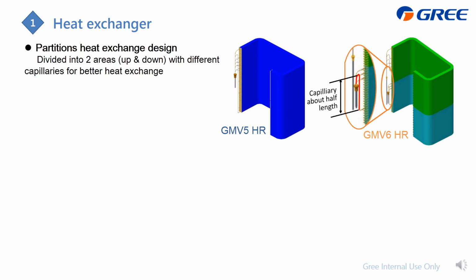For this heat exchanger, it is the same as the GMV6 heat pump series, so I just copied from that for your reference. About the heat exchanger, compared with GMV5, GMV6 improves or upgrades lots of points. First is the partition heat exchanger design. For the GMV5, this is the outdoor heat exchanger. You can find that this is the outdoor distributor, and the whole outdoor heat exchanger is just one. And for GMV6, we divide it into these 2 partitions.